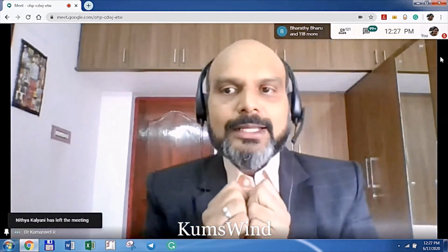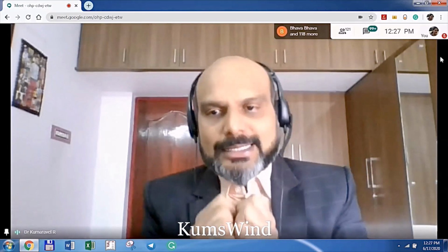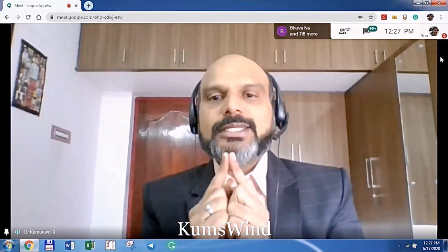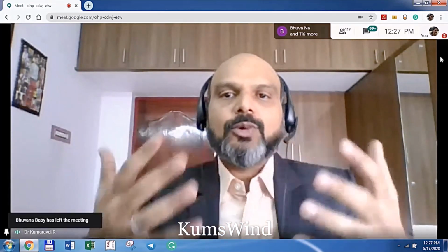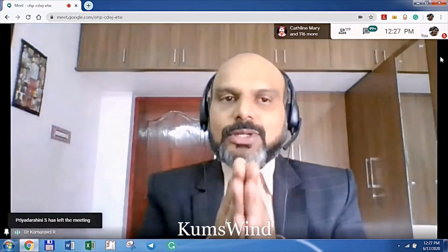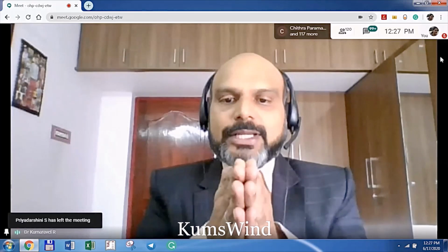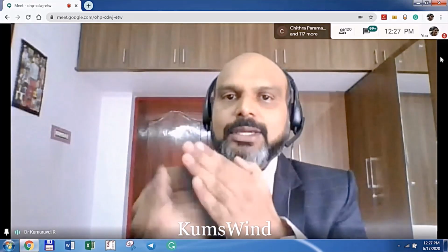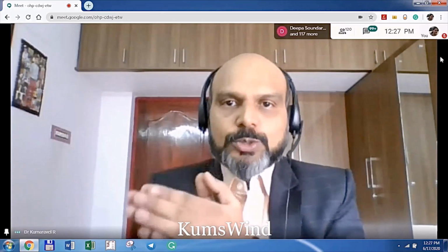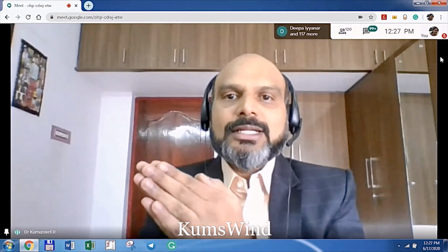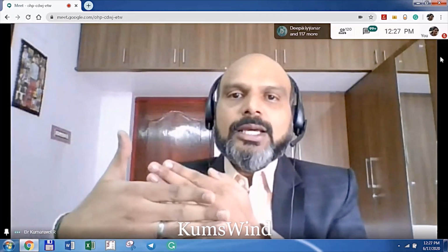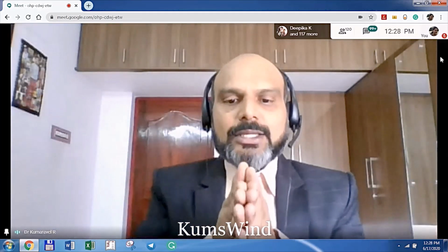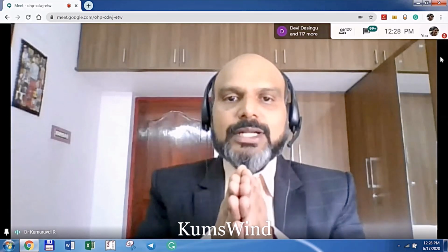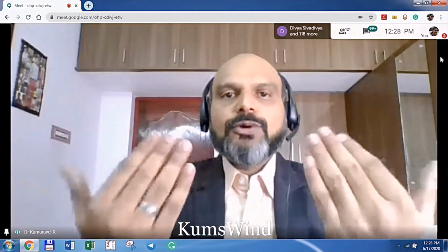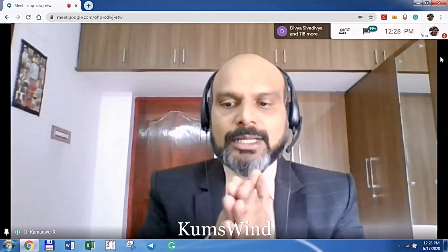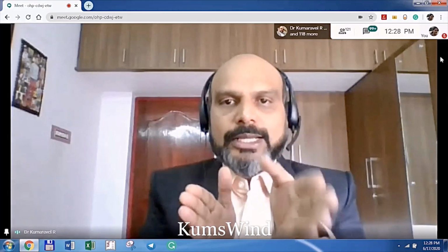The second question was about safe operation. Does wind direction affect the wind turbine? Yes, definitely. It affects it in two ways. One is in terms of power performance, because why do we need wind energy? To harvest more power. So if your wind turbine is facing a different direction than where the wind is coming from, you definitely lose power. The other, more disastrous effect is on the blades, which are rotating. When the nacelle directly faces the wind direction, the rotating blades get a uniform loading. But if there's a slight deviation, say 20-30 degrees from the actual wind direction...